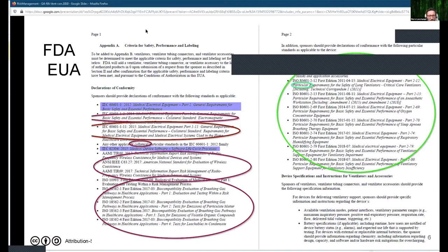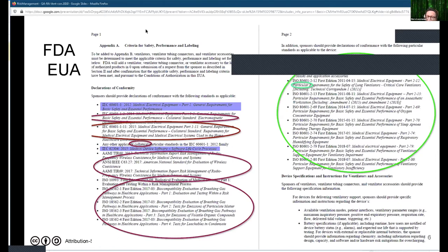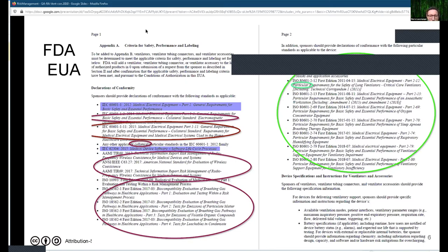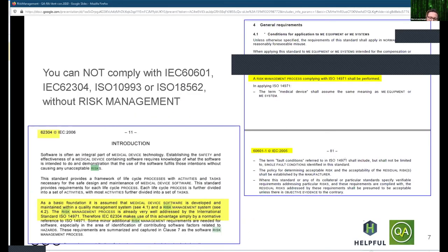What they list are general standards — the blue ones — and collaterals, which are standards that apply across all sorts of medical devices but for a specific topic, like the one I've circled in red, which covers electromagnetic immunity and biocompatibility. Then you have the particulars — the green circled ones — which are all specific to ventilators. But there's nothing about risk management. ISO 14971 is not in this list. Nevertheless, if you want to comply with 60601, 62304, and the biocompatibility standards, you have to have risk management. So even if the FDA did not write it in the list of requirements in the EUA, it's implied by the other standards they listed.